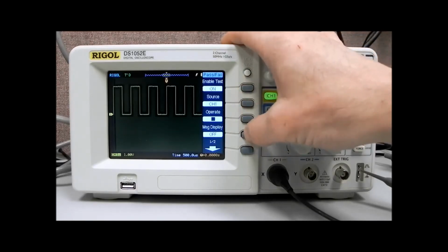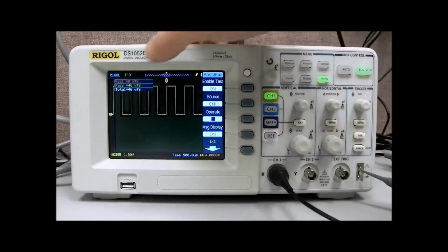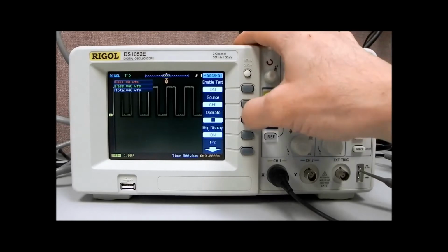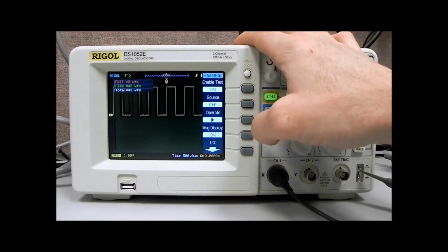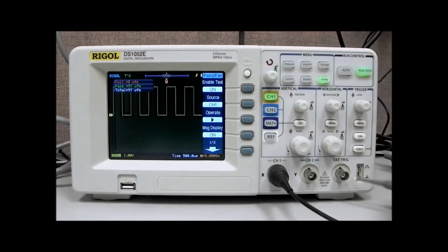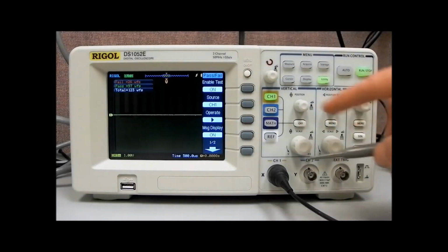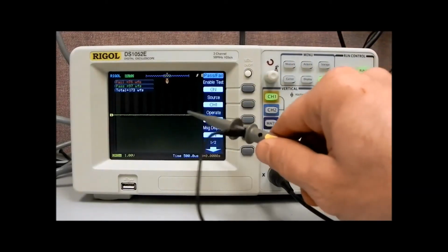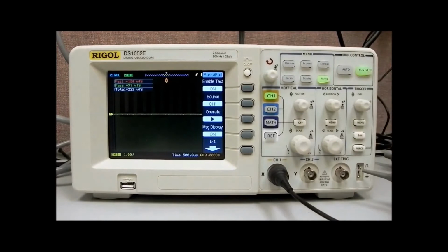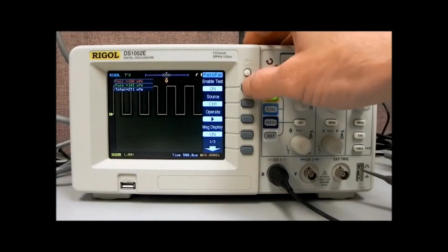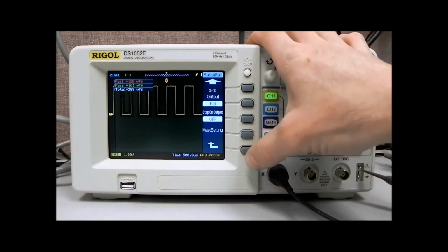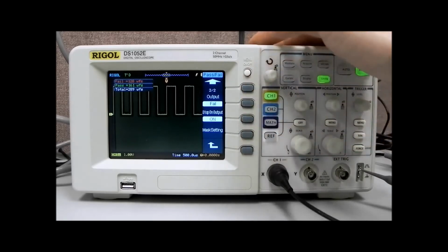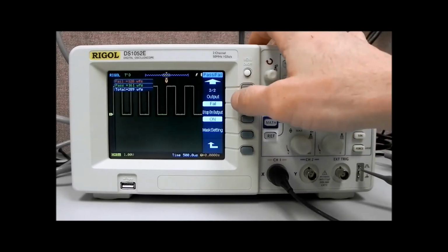We can pick the source. We can turn a message display on, which is going to give us a number of fails, number of passes, and then the total number of waveforms. So we can operate that, and you can see that'll increment. And then if we go to a fail, now we have a number of lines that are outside of that original mask and setting. I'm going to just turn that off for a second, and also turn the stop on output, and we're going to have the output on fail.